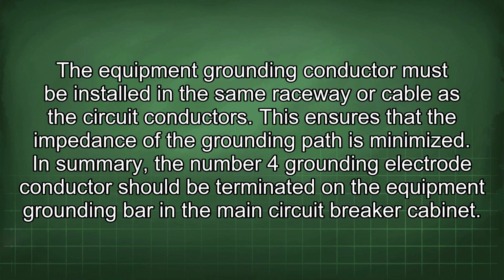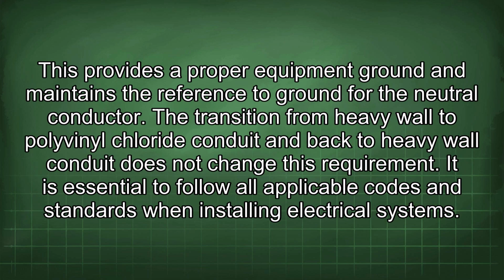In summary, the number 4 grounding electrode conductor should be terminated on the equipment grounding bar in the main circuit breaker cabinet. This provides a proper equipment ground and maintains the reference to ground for the neutral conductor.